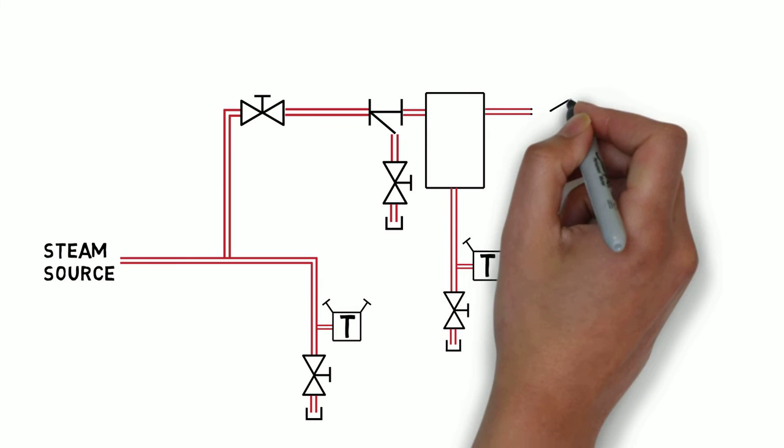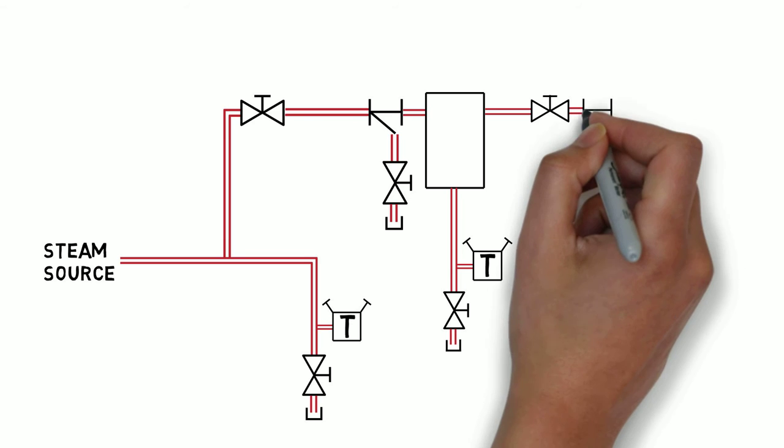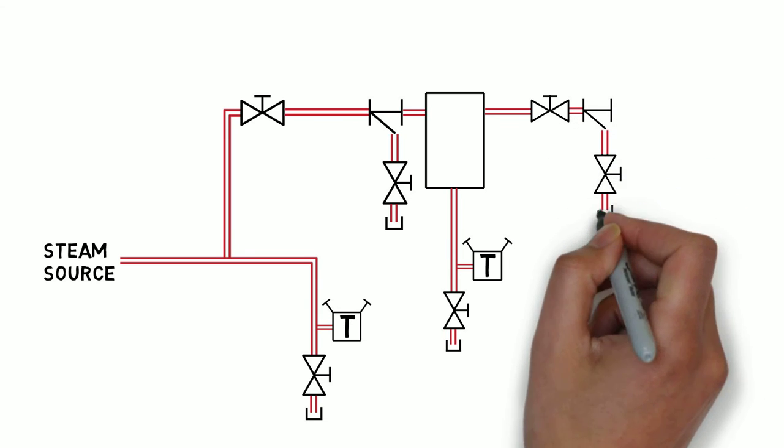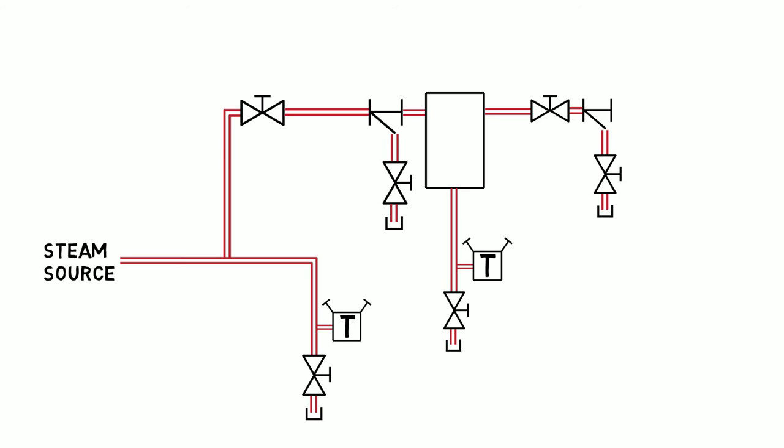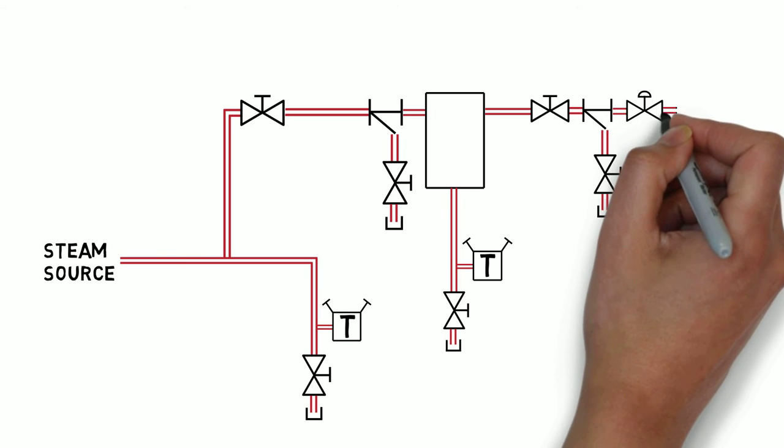From the steam separator, steam goes through a process isolation valve and is piped to a strainer with a blowdown valve. It next travels through a control valve and another isolation valve.